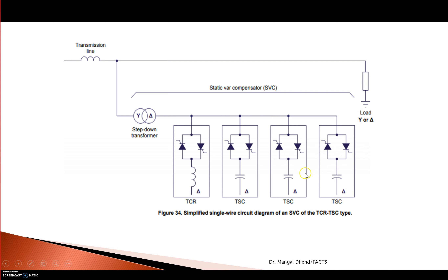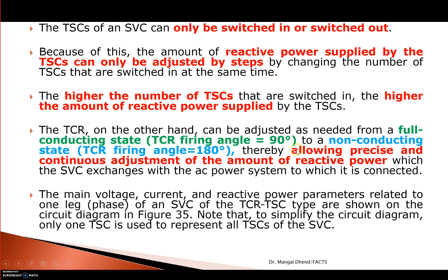Suppose you want to supply 25 KVAR. When 2 TSC banks are on they supply 20, but the third bank would add 10 giving 30. So switch the third TSC on making total 30, then use TCR to generate 5 KVAR, giving 30 minus 5 equals 25 KVAR. Like this, smooth control can be achieved with TCR in combination with TSC.